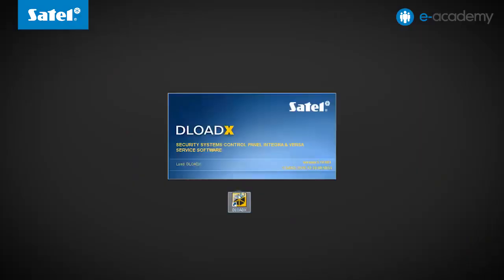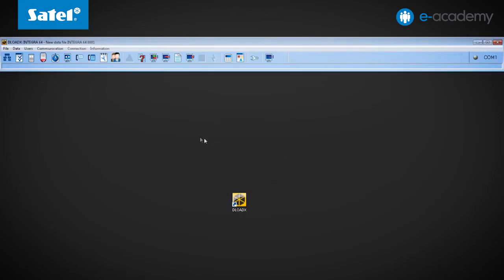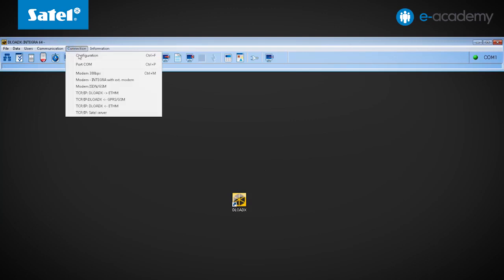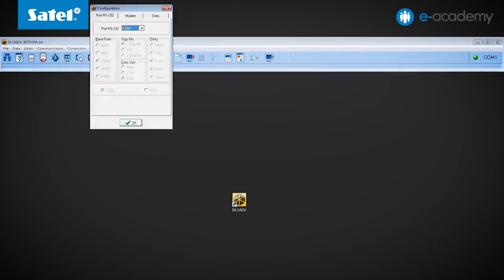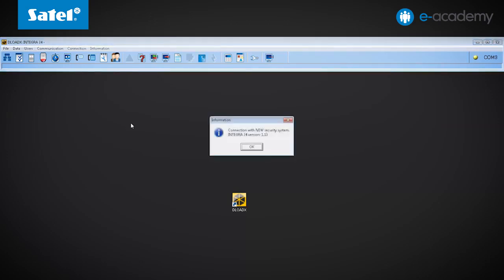Once this is done, go to the computer and start the DLOADX program. Open the Connection tab and enter the Configuration item. Then, in the Port RS232 tab, select the number of the port on which the converter is installed. Press OK to confirm your choice. The COM port icon activates in the upper right corner of the screen — the green indicator confirms that the port is active.